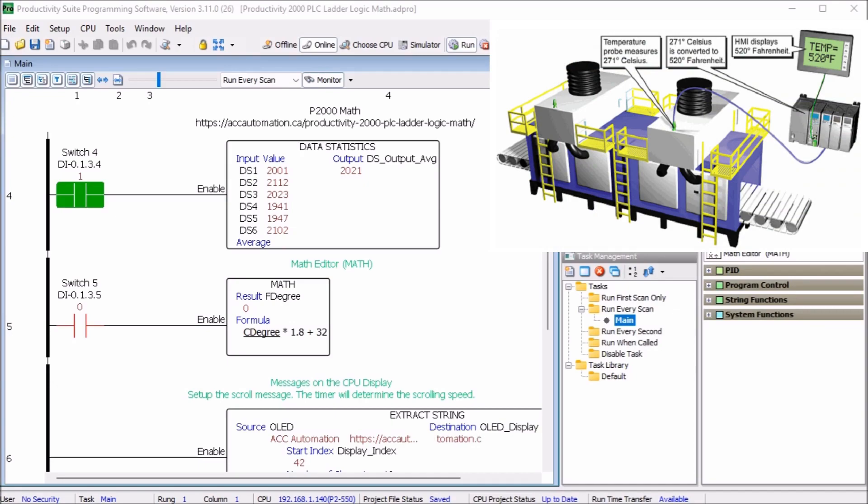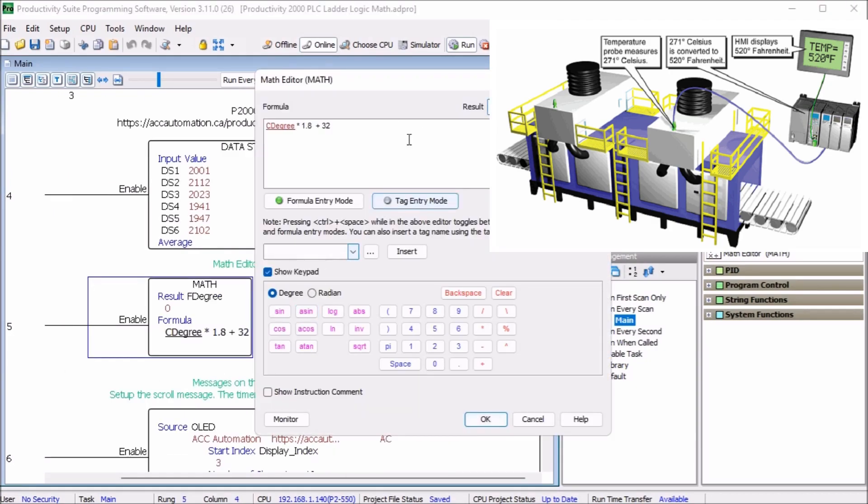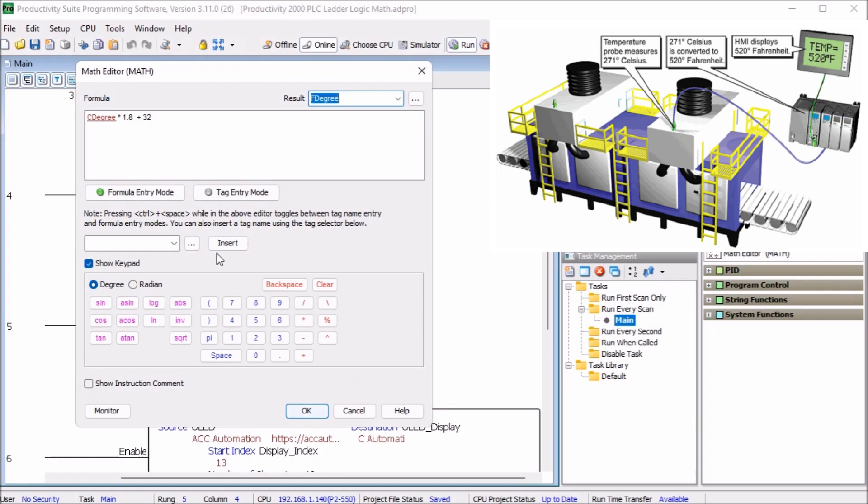Now in our example, we will take the oven temperature in degrees celsius which is 271 and convert this to fahrenheit degrees 520. The formula we will be using is degree C times 1.8 plus 32. Now the tag name is entered by selecting the tag entry mode button or by selecting the tag name and hitting the insert button. Tag names are highlighted in red. Formula entries are in black and you have to remember that the order of operation is effective for the formula.